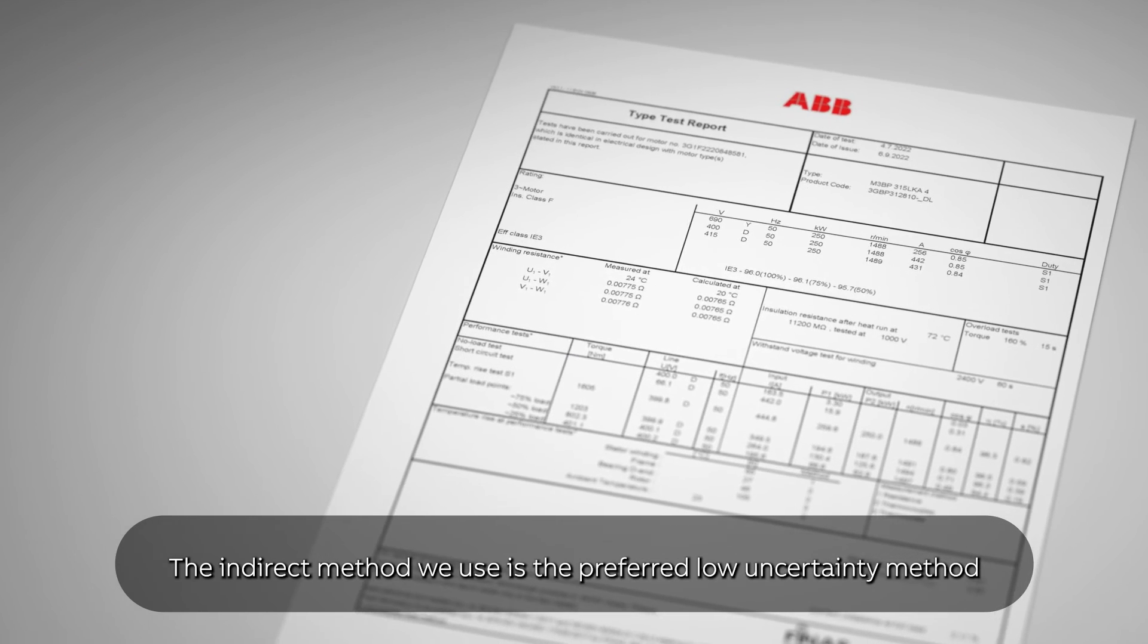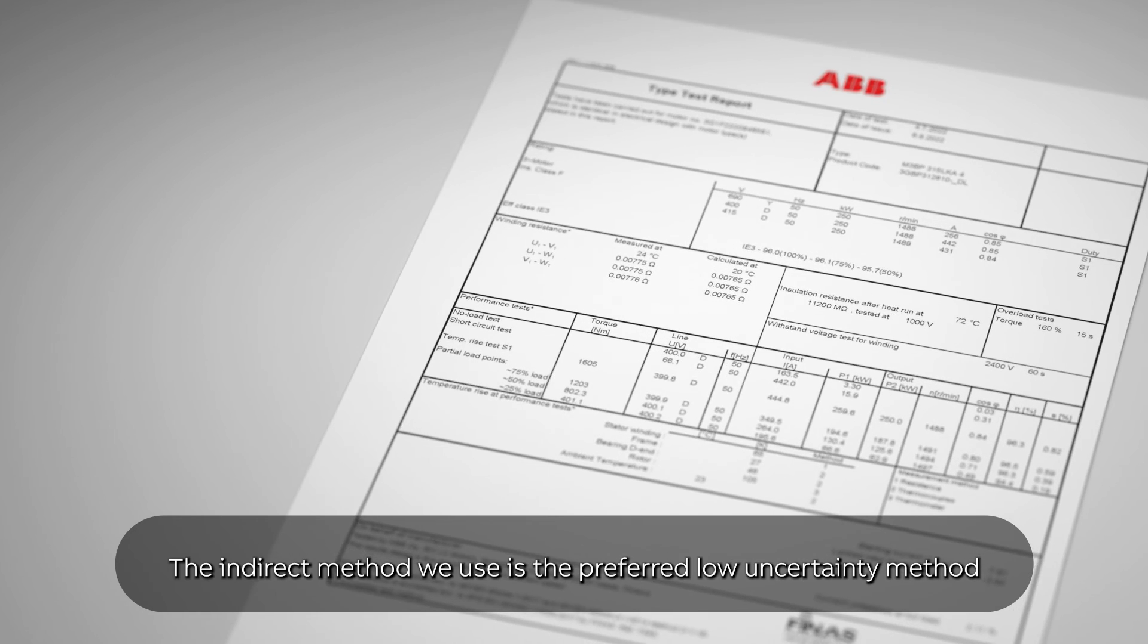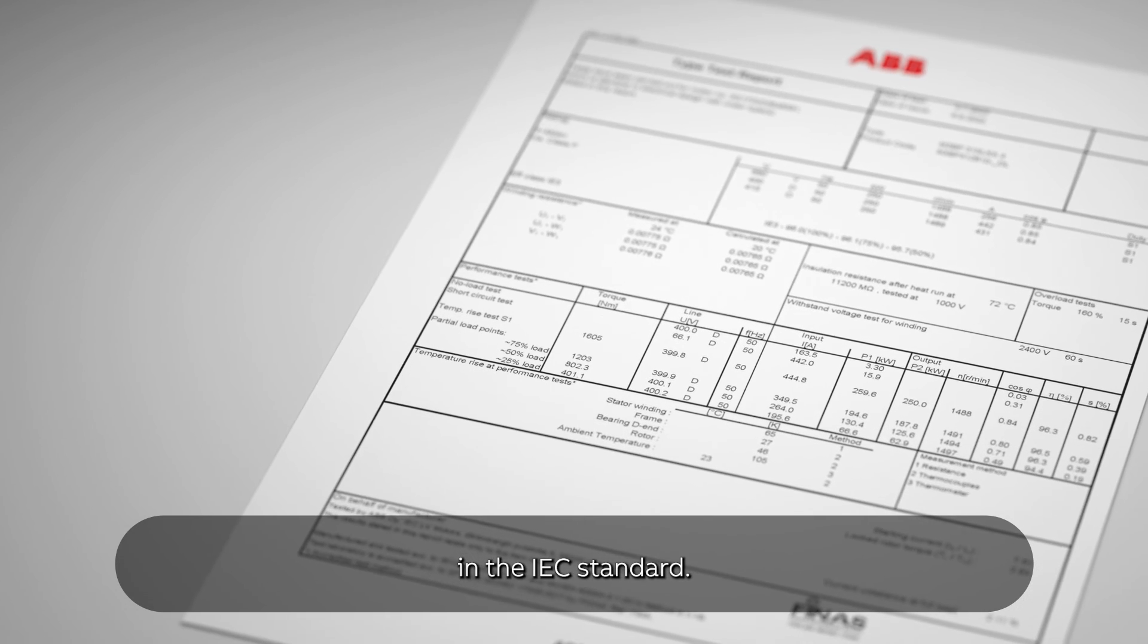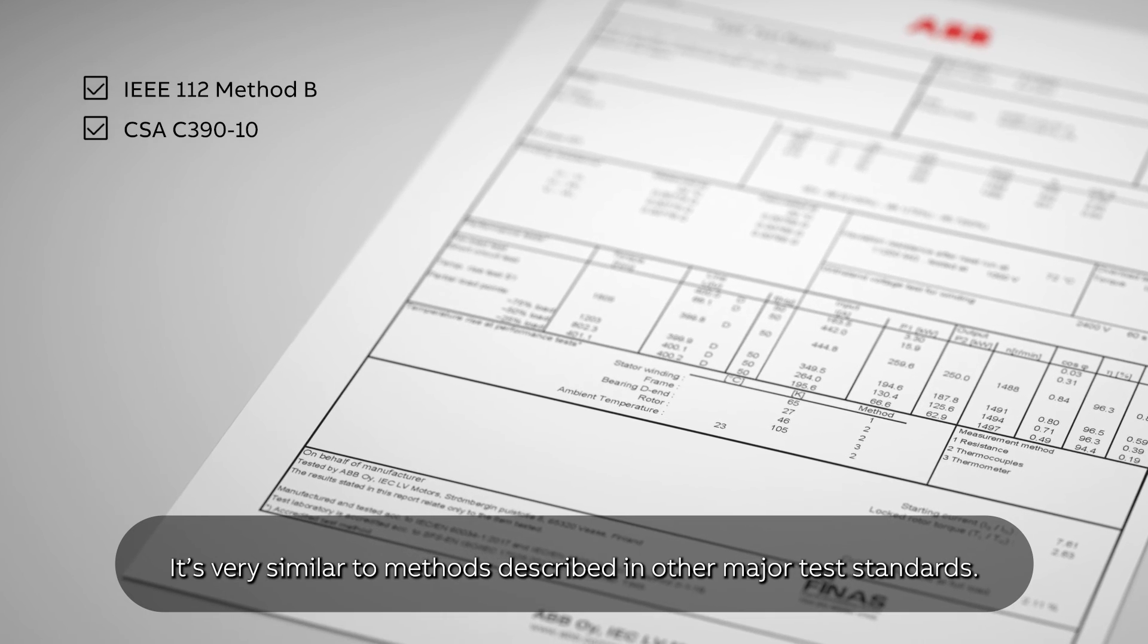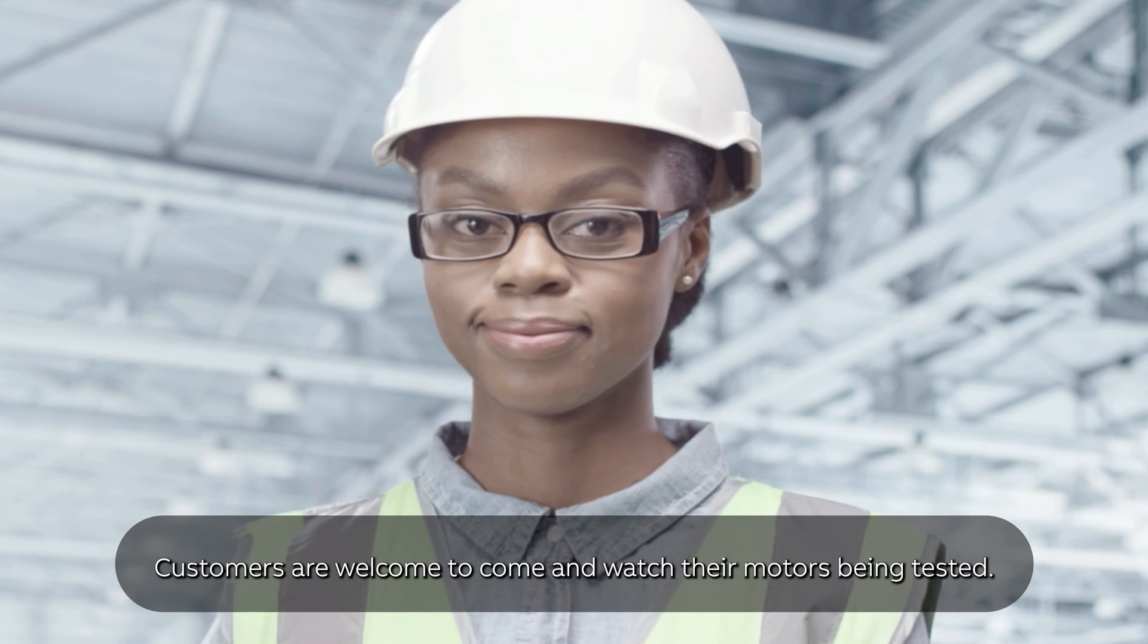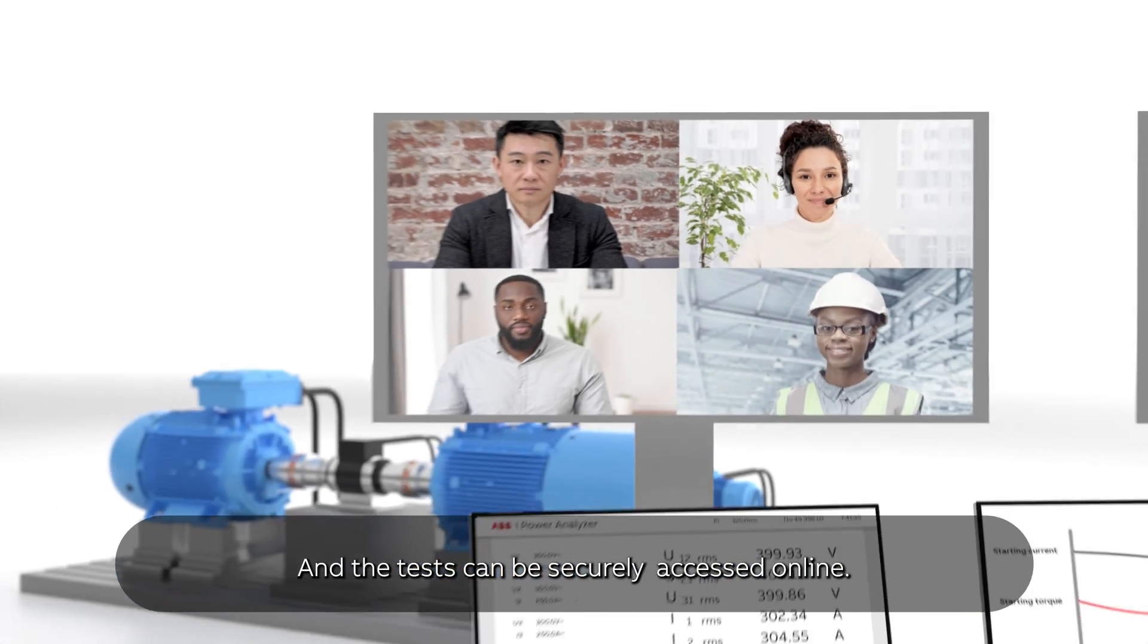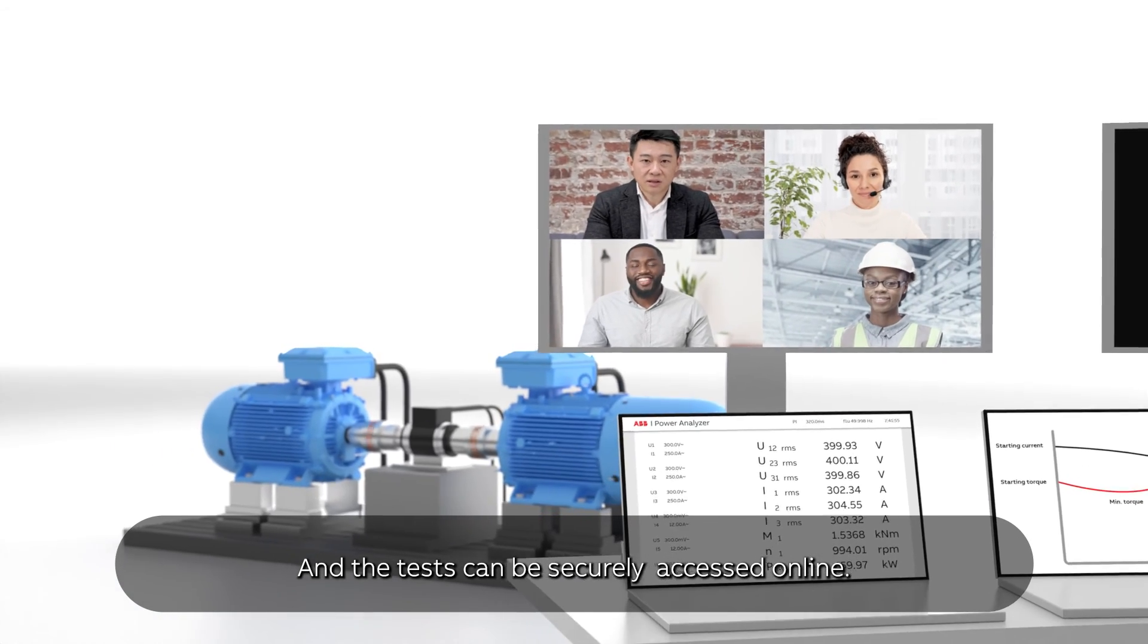The indirect method we use is the preferred low uncertainty method in the IEC standard. It's very similar to methods described in other major test standards. Customers are welcome to come and watch their motors being tested and the tests can be securely accessed online.